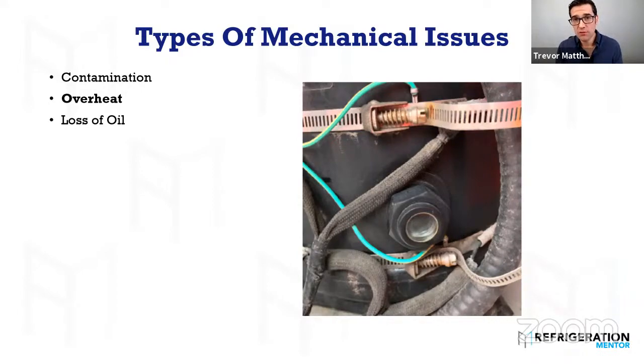And after you remove a compressor, especially if it's hermetic, you need to check how much oil was in that compressor. Nobody's doing this, because I didn't do it before I worked for a compressor manufacturer. I didn't do it because I didn't know I was supposed to. But if there's no oil in that compressor and you can't find a leak, where's the oil? And what happens if you keep replacing compressors, you're putting more oil in the system, and all of a sudden the oil comes back and smashes the compressor from a slug. Then you get continued repeat failure. So you need to figure that out. You need to measure oil and compare it to the manufacturer spec of oil.